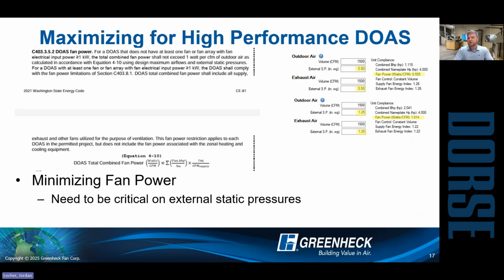The other thing that we see, so code driven, is really minimizing fan power, right? So the idea is, okay, we're using a very effective ERV. We're recovering as much energy as possible. At the same time, we don't want to forget about our fans. So we don't want to burn more energy than we need to moving the air across that ERV, right? This is written into the Washington State Code. So I have that section there, basically requiring less than 1 watt per CFM. So I just threw an example up there on the top right.